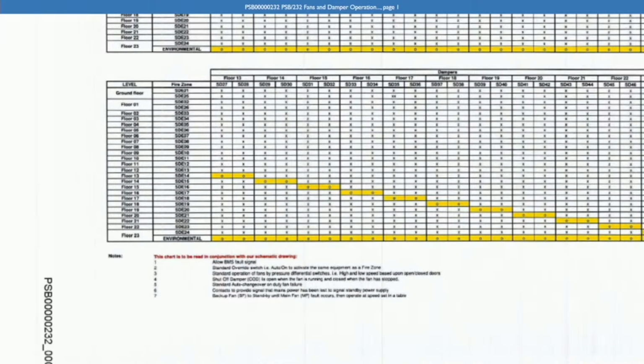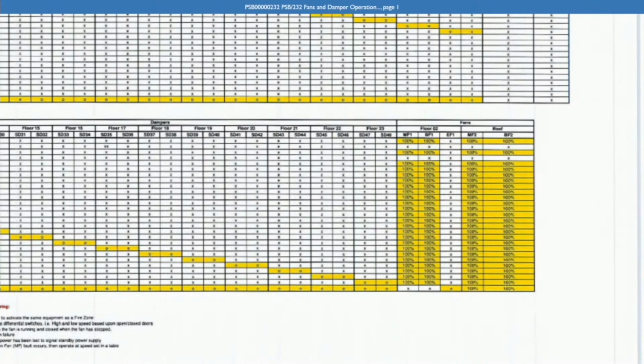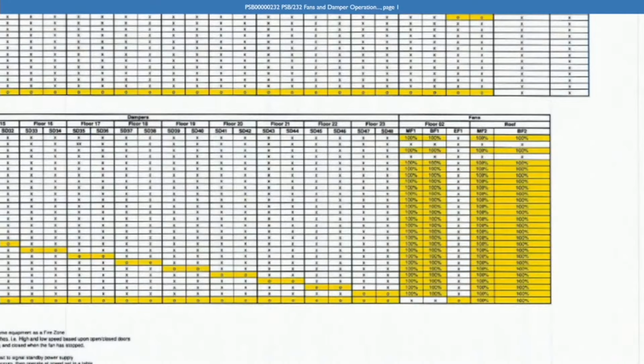Yes. So where there's an X, are we to take that as the standard operation of the fan? Sorry, if we go along to the right, it's been cut off on this screen view. If we go to the right of the bottom table, where you've got an X rather than 100%. Yeah, that's for environmental mode. Right. So on that very bottom row, when environmental mode is activated, your main fans are off, and your environmental fan is on.